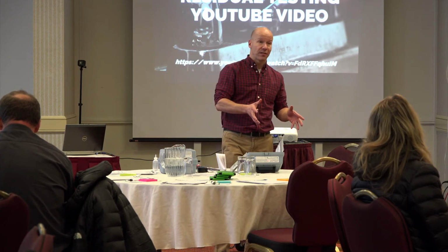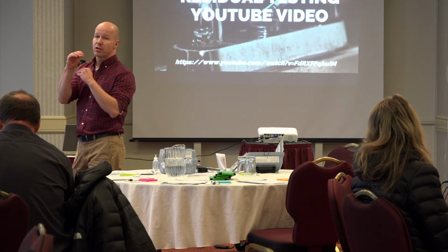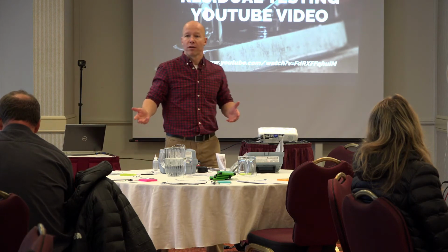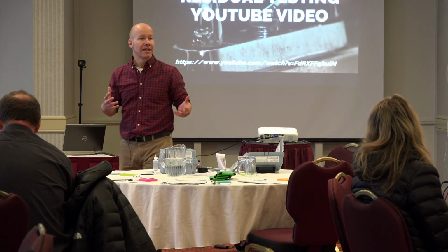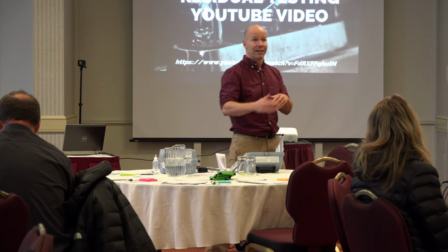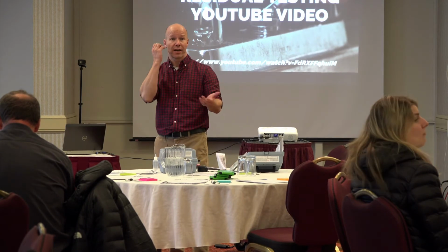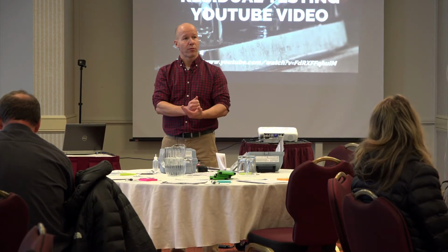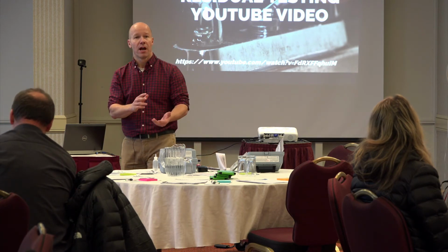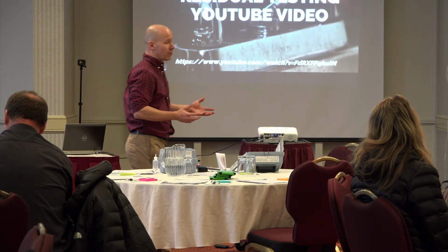So remember, this is a field kit. They're not going to be super accurate. There's a range. So if you told me that you got 0.51 one day and then 0.56 the next day, that's the same number. That's close enough in the range with these kits. I wouldn't call that a change. If an operator called me, I had one guy used to try to keep it at 0.50. If he got 0.49, he'd turn up the chlorine. If he got 0.51, he'd turn it down. He drove himself crazy for years. But the kits are not that accurate. Remember, this is a field kit.